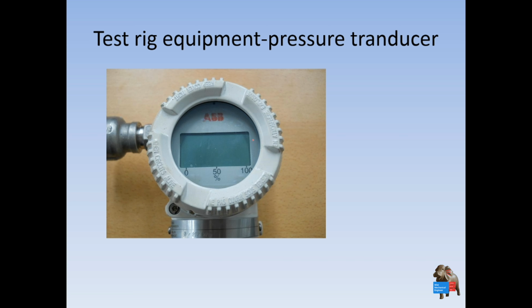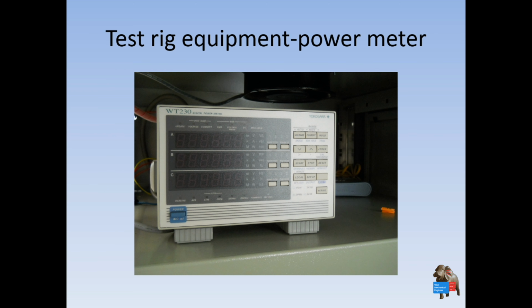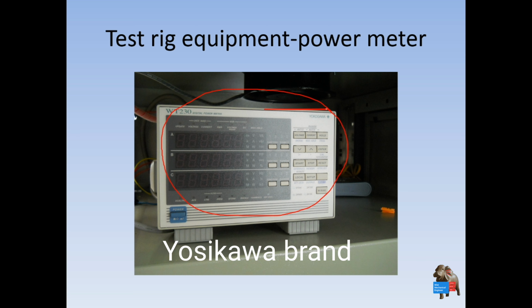And then you also have a pressure transducer. This is an ABB brand. It measures the suction and discharge pressure of water during testing. And then you also have a power meter here. This power meter measures how much power is actually absorbed by the AC motor during testing at a specific flow capacity.